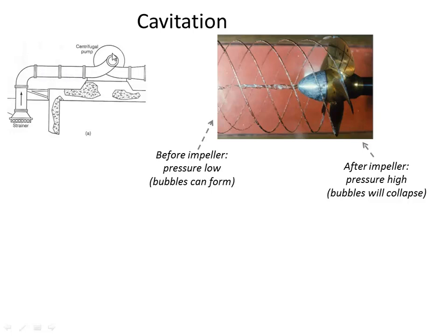And it's actually inside of the pump that the situation is most precarious, because the impeller has several curved vanes inside, and as it accelerates the flow through the pump, there is a very high pressure side of the pump and a low pressure on the back side of the vane. It's a little bit like an airplane wing, so that there are huge pressure differentials inside of the pump. And so the cavitation can occur inside of the pump even though the rest of the bulk liquid may be far away from the vapor pressure.